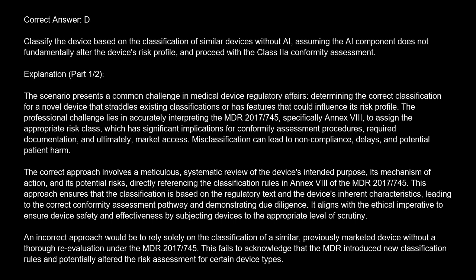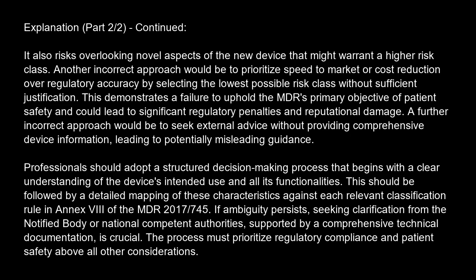An incorrect approach would be to rely solely on the classification of a similar, previously marketed device, without a thorough reevaluation under the MDR 2017/745. This fails to acknowledge that the MDR introduced new classification rules and potentially altered the risk assessment for certain device types. It also risks overlooking novel aspects of the new device that might warrant a higher risk class. Another incorrect approach would be to prioritize speed to market or cost reduction over regulatory accuracy by selecting the lowest possible risk class without sufficient justification. This demonstrates a failure to uphold the MDR's primary objective of patient safety and could lead to significant regulatory penalties and reputational damage.